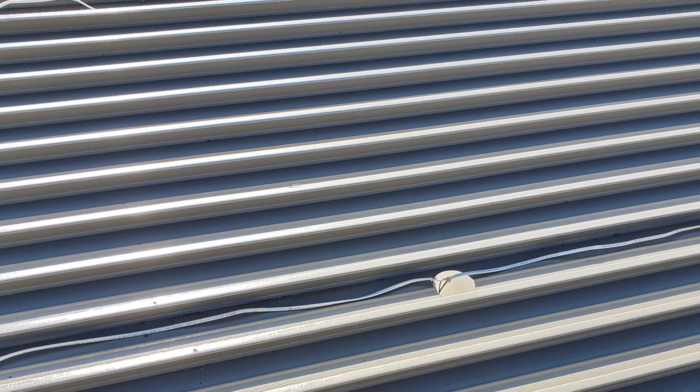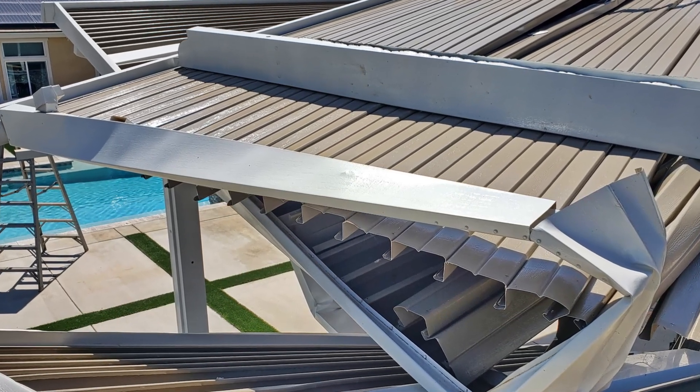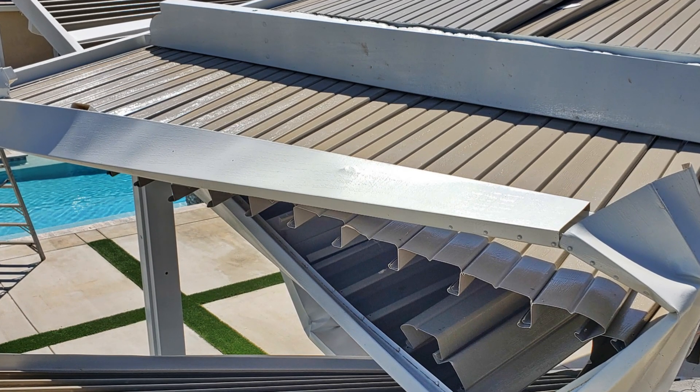The required aluminum flashing covers were not installed, leaving the Romex wire exposed to direct sunlight, which would have caused fixtures to leak as well as create a very hazardous situation in the future. Luckily, the family had just left the backyard and entered the home when this failure occurred. They were all incredibly fortunate that no one was hurt or killed.